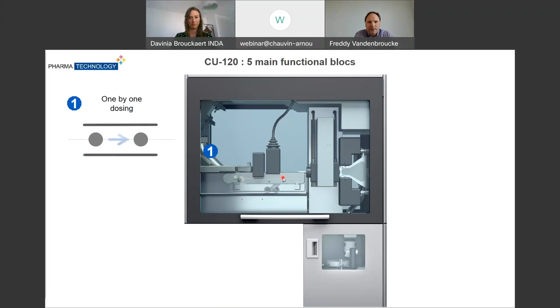Now let's look at the CU120 and its five functional blocks. The first block performs the dosing and alignment of the product. There is a hopper where the product is dropped in, and a linear feeder combined with a centrifugal bowl for high-throughput dosing and alignment of the tablets, which go out in a single row onto the conveyor.